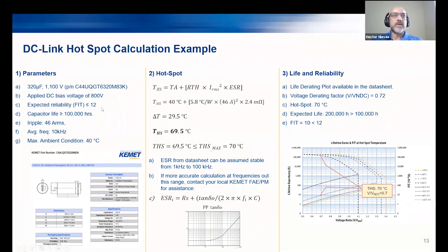And then a voltage of 800 volt DC is applied in the line of the capacitor. This is a DC-link capacitor as well. Expected reliability is equal or less than 12, and the capacitor life expectancy is at least 100,000 hours.